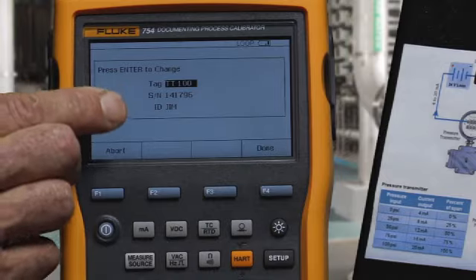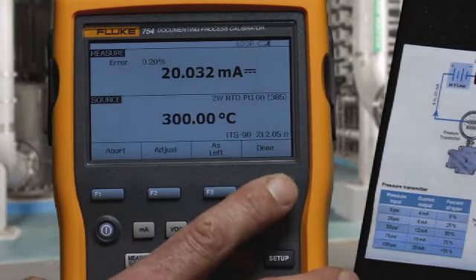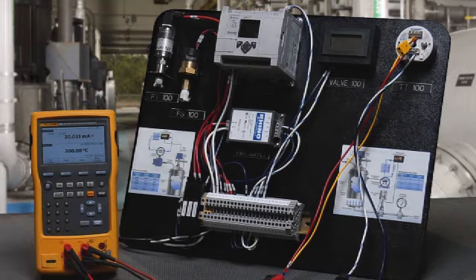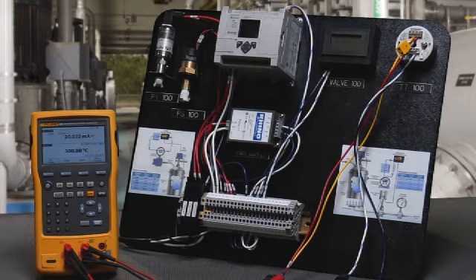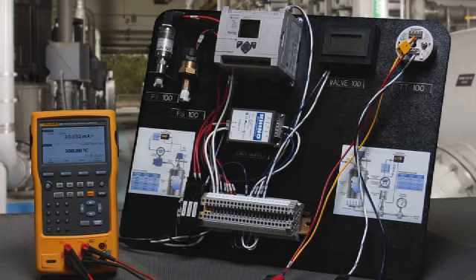Tags, serial number and ID of who did the work. Done. And we're done because it passed the test. And we have completed documenting the performance of this RTD transmitter using the 754 documenting process calibrator.